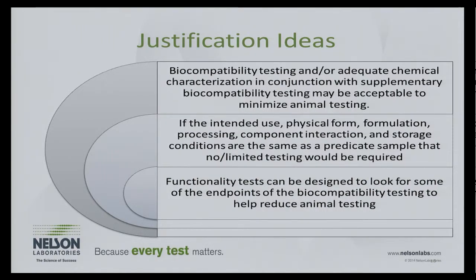This next one is also one that we've used successfully. In fact, I try to get people, when they're doing their functionality tests, to call me first, okay? Because a lot of times the functionality is done by somebody else, and then the preclinical testing is done by somebody in another department, and they've wasted some of their endpoints in their functionality tests for biocompatibility. We can put endpoints in functionality. We can put hemocompatibility.